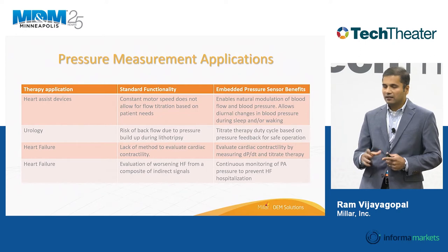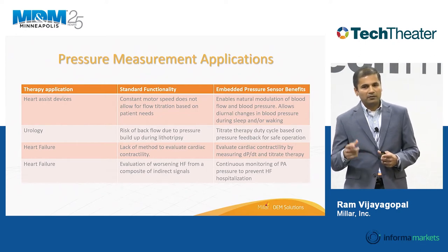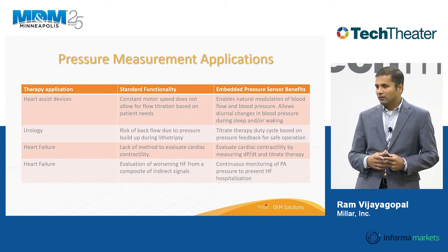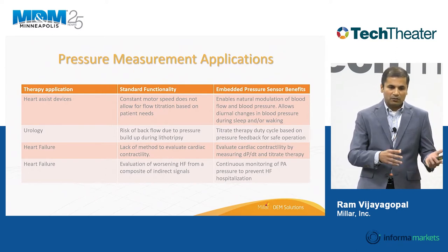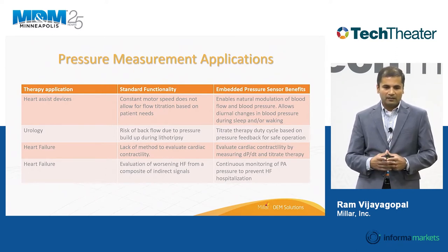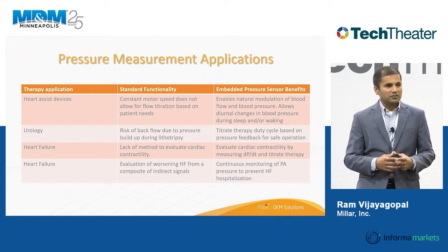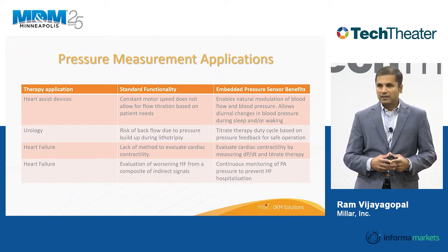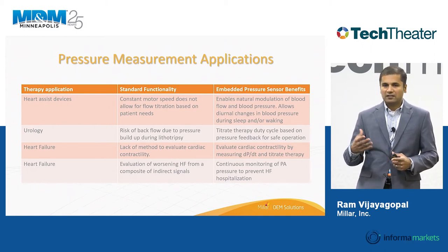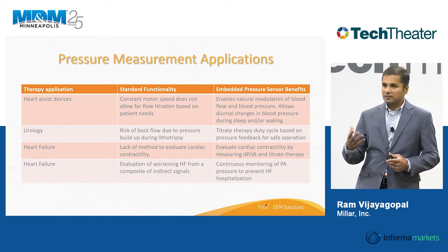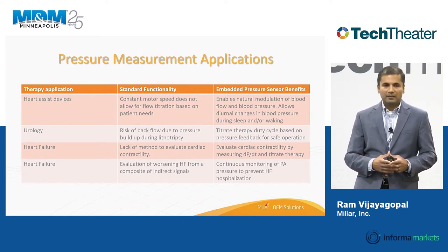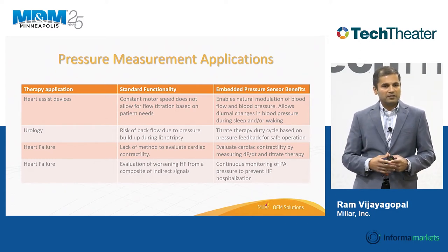Historically, a lot of these devices have a motor with a pump, and all these devices are working at a fixed speed — that's the first generation. Going forward, a lot of these companies are seeing the need to adjust therapy based on the physiological needs of the patient, and that's where a pressure sensor comes in. Pressure sensor feedback enables more physiological modulation of pressure.